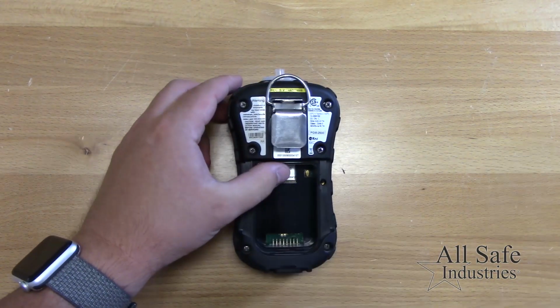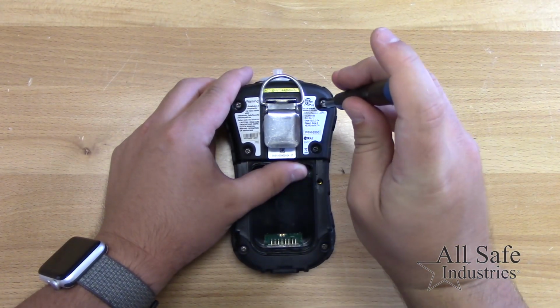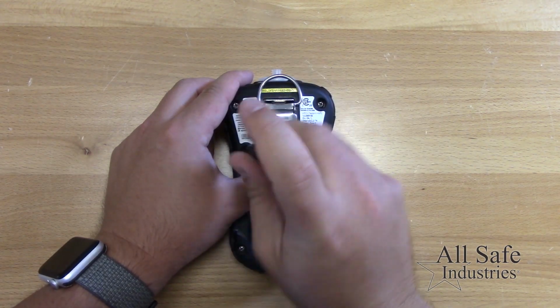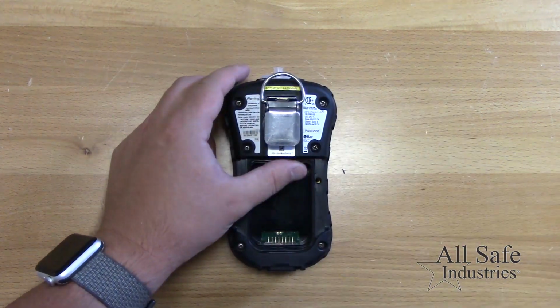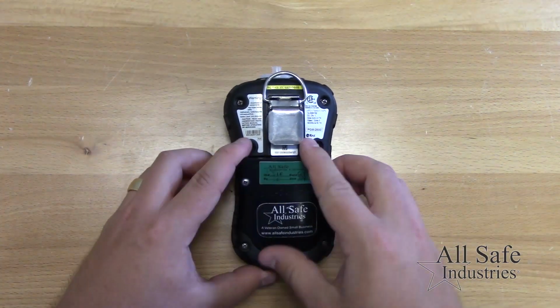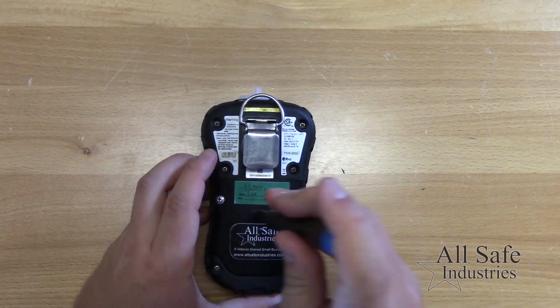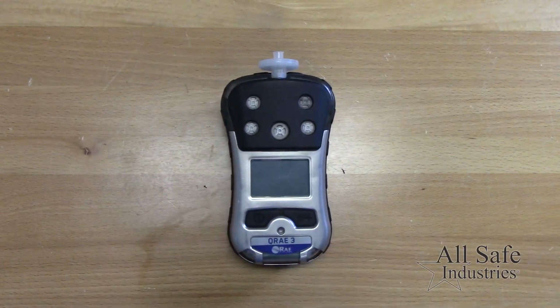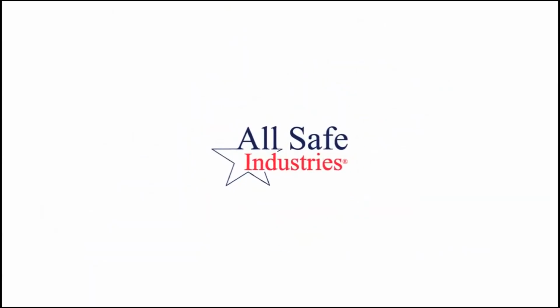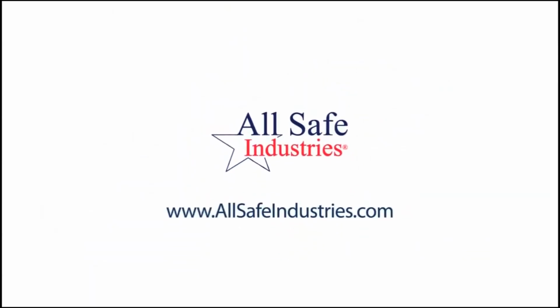Reattach the gas plate and tighten the screws on the back of the meter and recalibrate. Please note, when replacing the O2 sensor, wait 24 hours to allow the new sensor to acclimate to air before performing the first calibration. For anything beyond routine use and maintenance, please contact our service team or visit our website.